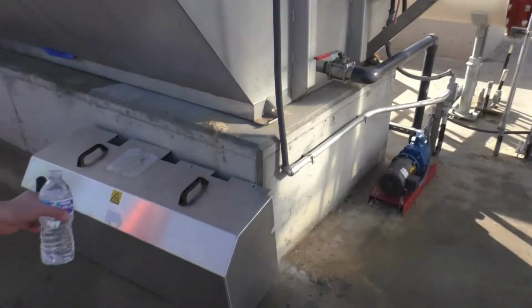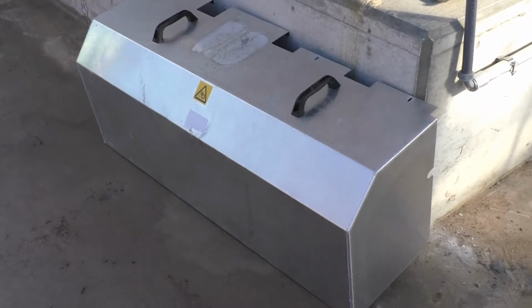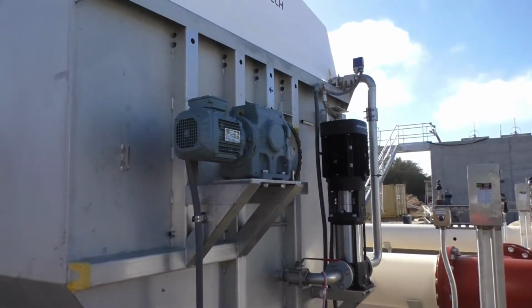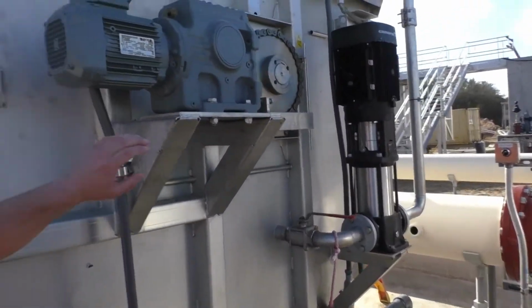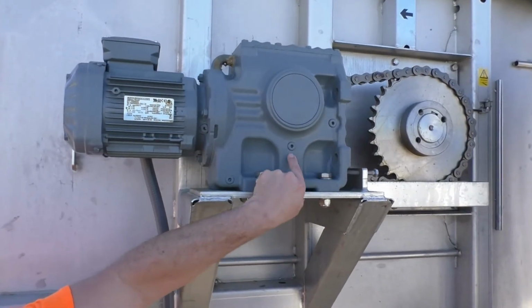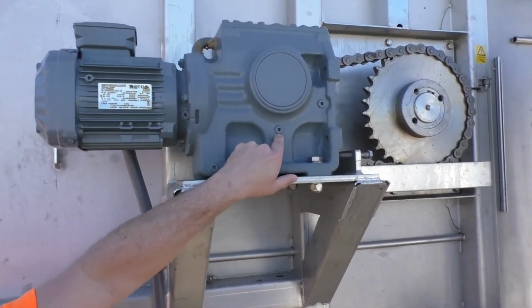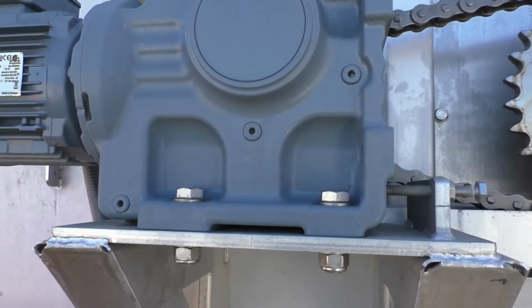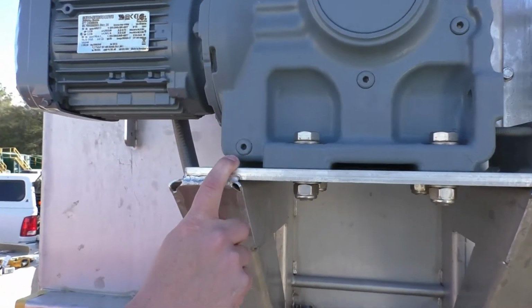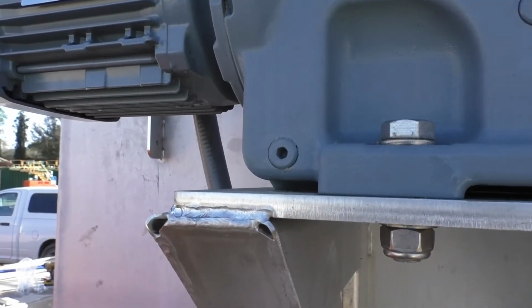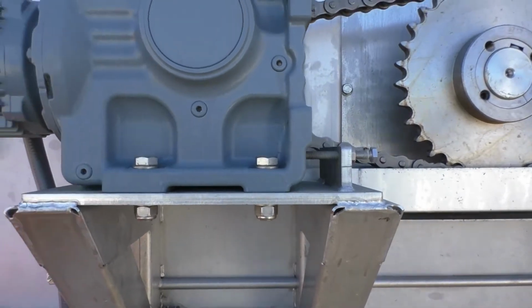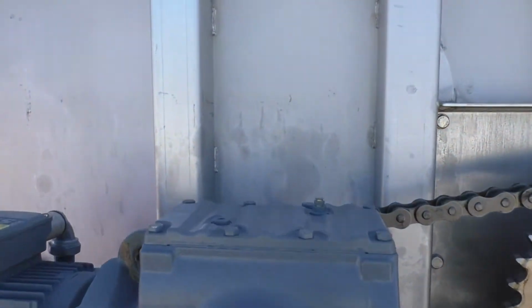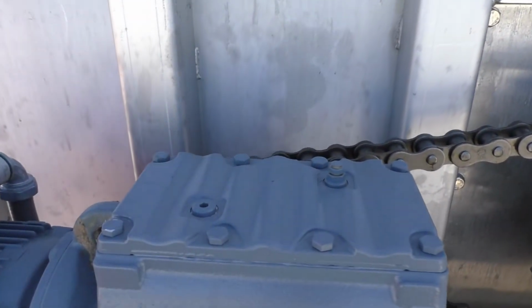So that's the cover right there. It goes over the gearbox. It's similar to your old unit. Gearbox, you have 3 Allen screws. The one in the middle is your oil level. Change your oil every 3 years. This is obviously your low plug to drain it. You do have a plug on the very top up here that you can fill it if you need to, or when you do change your oil.